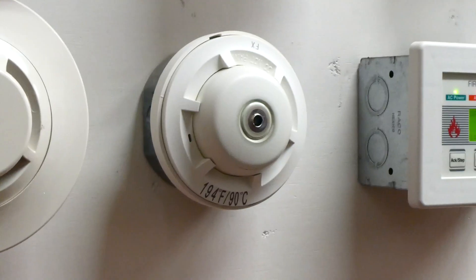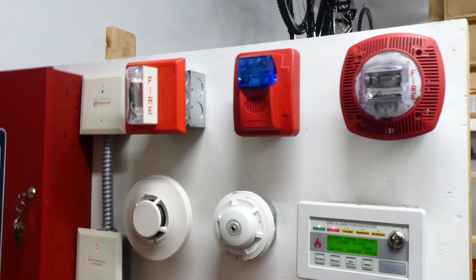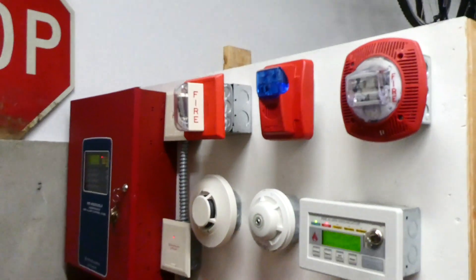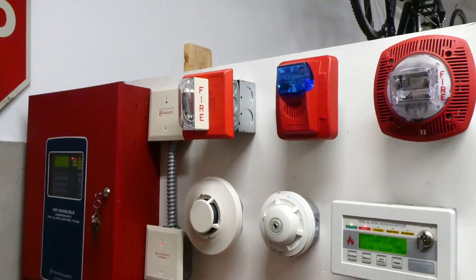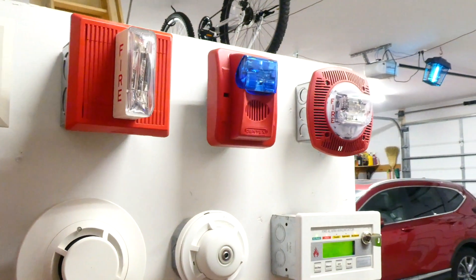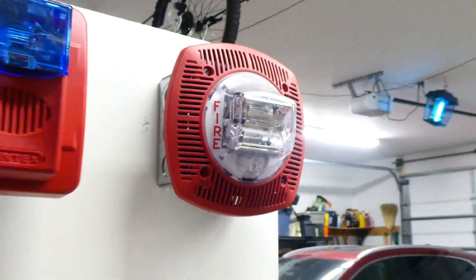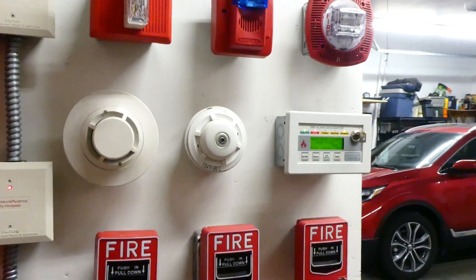Let's hear it. Please leave the building and report to the designated assembly area for your group. May I have your attention please — an emergency has been reported in the building; while this is being verified, please leave the building and report to the designated assembly area for your group. And there it is — that heat detector is now permanently activated.